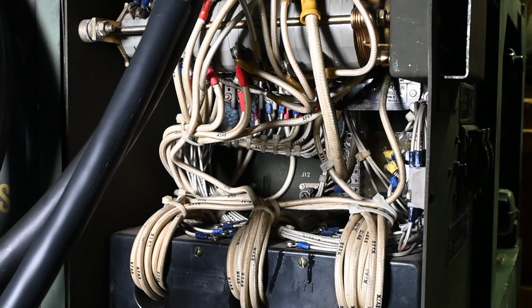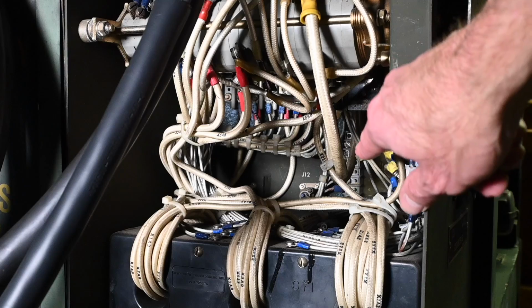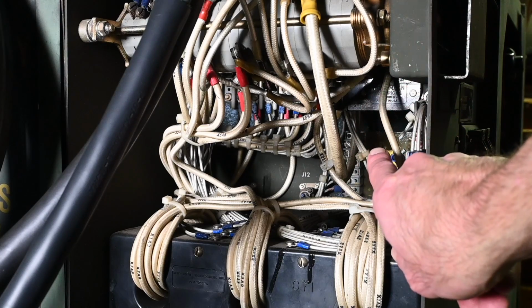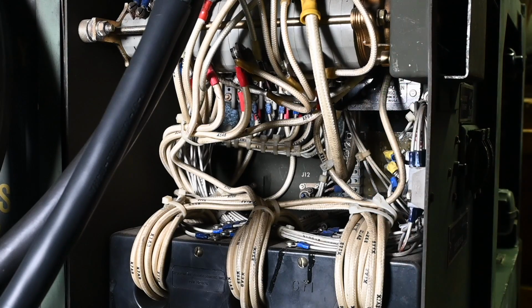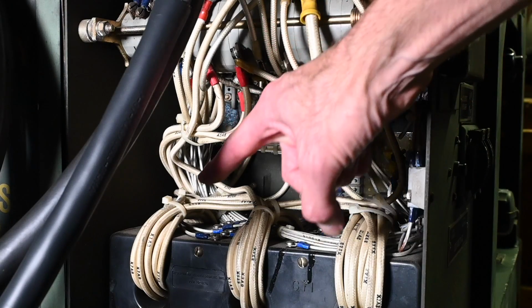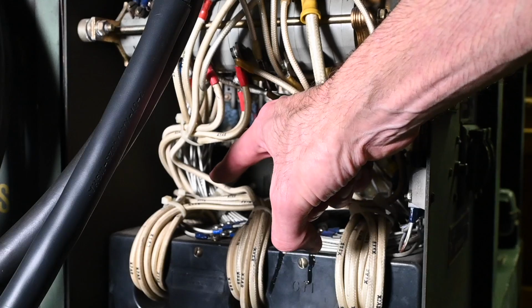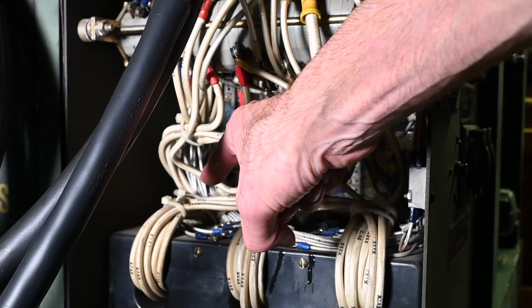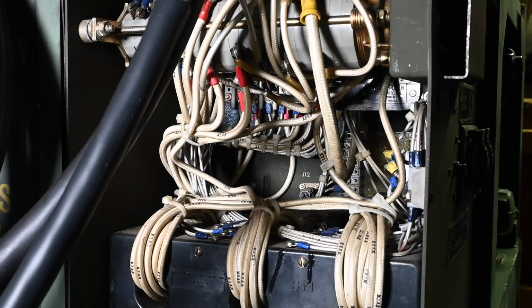So on the back wall of this box, right back in there, there's a circuit board, a little bit hard to see, marked as A4. It's a bridge rectifier assembly, basically a 3-phase bridge, and it also has a resistor on that circuit board, which is part of the field flash circuit, and we'll see that on the schematic. But the bridge rectifier is part of the voltage regulation circuit. Now down in this corner, you really can't see it, but on the bottom area of this box, mounted in the corner, is an inductor. It's marked as L1 on the schematic. It's actually 3 individual inductors. It's part of the voltage regulation circuit.